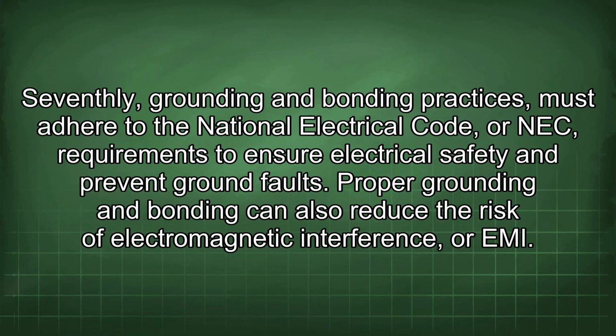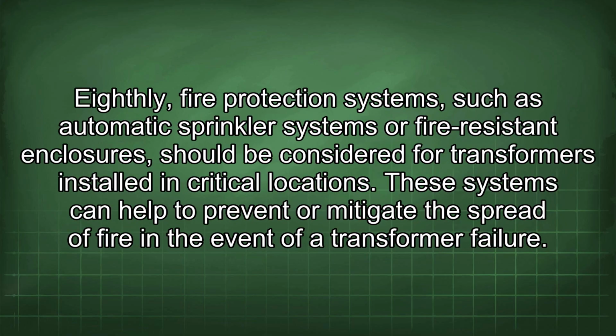Seventhly, grounding and bonding practices must adhere to the National Electrical Code, or NEC, requirements to ensure electrical safety and prevent ground faults. Proper grounding and bonding can also reduce the risk of electromagnetic interference, or EMI. Eighthly, fire protection systems, such as automatic sprinkler systems or fire-resistant enclosures, should be considered for transformers installed in critical locations. These systems can help to prevent or mitigate the spread of fire in the event of a transformer failure.